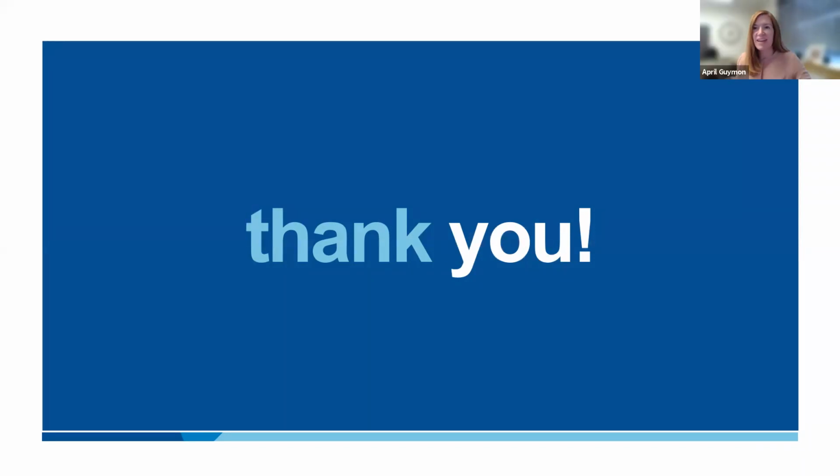I can take that one. That is a really great question. And I think the answer is going to be, it depends on which software you use and how well that software is implemented. Most of the software will have some ability to do some kind of tuning. So maybe there's some constants in those rules and algorithms we talked about that can be adjusted. So maybe a leaking valve isn't flagged until there's a 5-degree difference, or maybe you want it to be a 10-degree difference and only catch the really bad ones at first. So they usually have some kind of flexibility where they can be adjusted to reduce noise or nuisance faults, faults that aren't right. So there's potential for that, but with a little bit of effort and some attention, they can usually get tuned in to be very accurate and very useful.